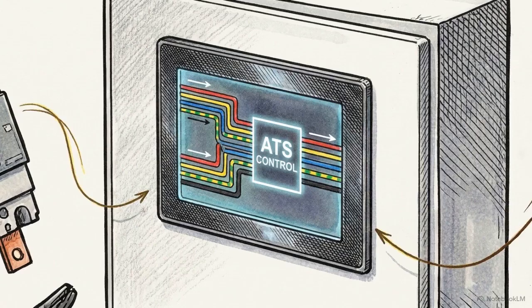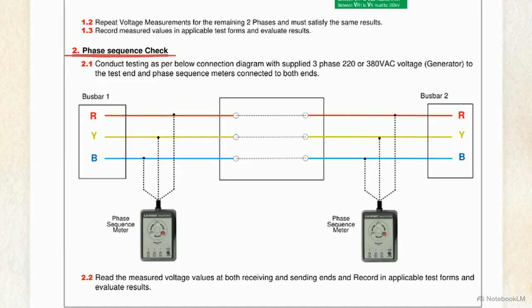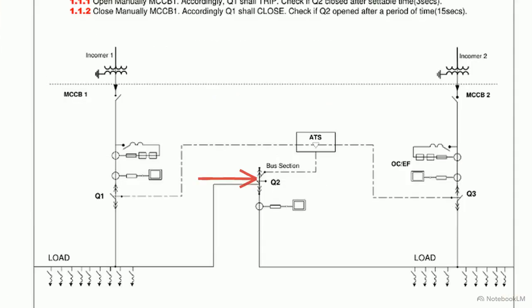The highest level of complexity in the ACDB is the automatic transfer switch, which dictates how the board handles 2 separate power sources. Before enabling any automatic transfer logic, engineers must verify the phase sequence across an open bus section to ensure both sources have matching rotation. Testing begins with incomer breakers closed and bus tie breaker Q2 open. The engineer simulates the loss of incomer 1.